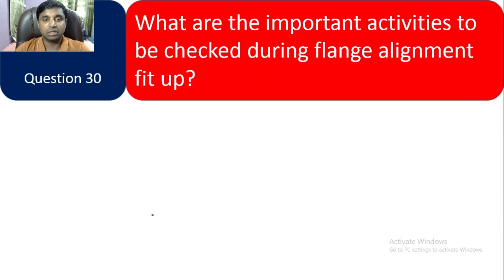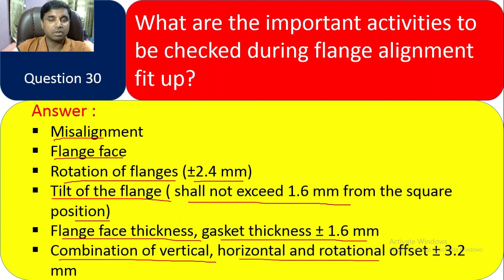Question 30: What are the important activities to be checked during flange alignment? You must check for misalignment, flange face condition, rotation of flange (±2.4 mm), tilt of flange (shall not exceed 1.6 mm from square position), flange face/gasket thickness (±1.6 mm), and combination of vertical, horizontal, and rotational offset (±3.2 mm). These 30 questions, along with the previous 30, cover 60 essential piping inspector interview questions.